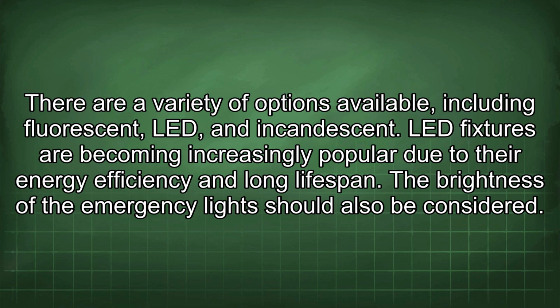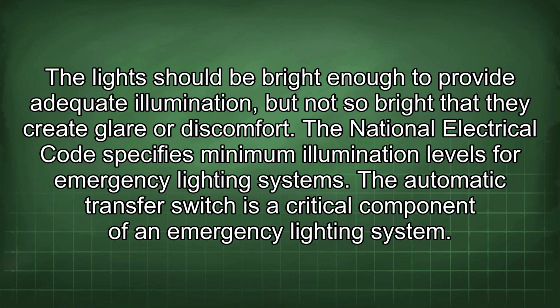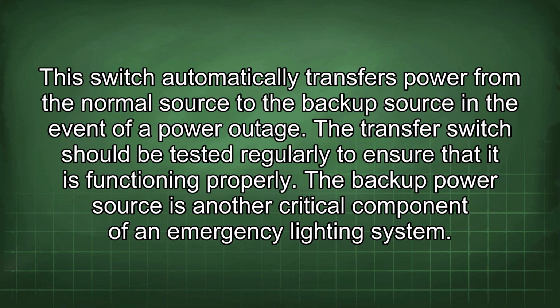The brightness of the emergency light should also be considered. The light should be bright enough to provide adequate illumination, but not so bright that it creates glare or discomfort. The National Electrical Code specifies minimum illumination levels for emergency lighting systems. The automatic transfer switch is a critical component of an emergency lighting system. This switch automatically transfers power from the normal source to the backup source in the event of a power outage. The transfer switch should be tested regularly to ensure that it is functioning properly.